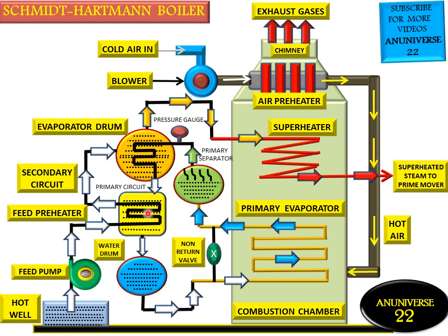The steam produced in this evaporator drum from the impure water is further passed to the superheater and then supplied to the prime mover. The high pressure condensate formed in the submerged heating coil is circulated through a low pressure feed heater on its way to raise the feed water temperature to its saturation temperature. Therefore, only latent heat is supplied in the evaporator.